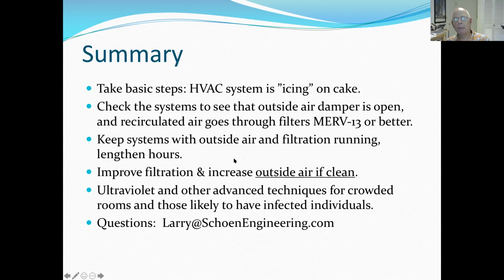The problem is I still want some overall turnover of airflow in that room, because even though you've directed it downwards, if it's a small enough particle to remain airborne, it just goes down to the floor, hits the floor, and comes right back up into the room. If it's not a very densely occupied floor, then you're not going to have a lot of exposure, so that's good. But I still want some ventilation turnover in that big room.